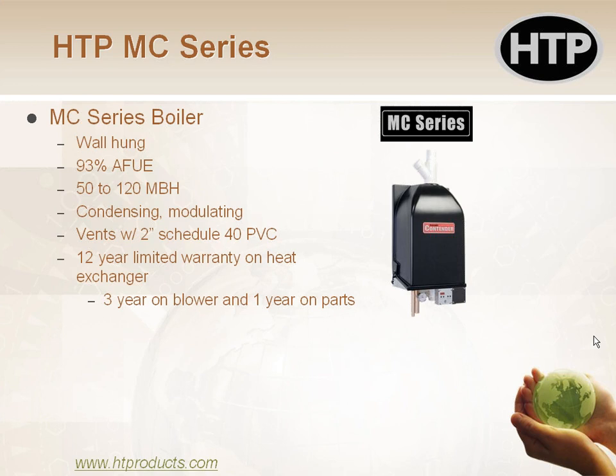So they're condensing, so we're grabbing some of that energy out of the flue gas, which is how we get up above 90%. Typically, when you're below 90%, you're probably not talking about a condensing boiler. When you're above 90%, you typically are a condensing boiler. I'm sure there's exceptions to that, but that seems to be how most manufacturers are set up. And it's modulating, which means that if I have a 120 MBH boiler, it doesn't mean I have on, off, 0 or 120. It means I can modulate between 0 and 120. Or maybe not 0, but say 50 and 120 or something like that. And I can hit various points in between there. So I can more appropriately match my boiler capacity to my actual load at a given moment.